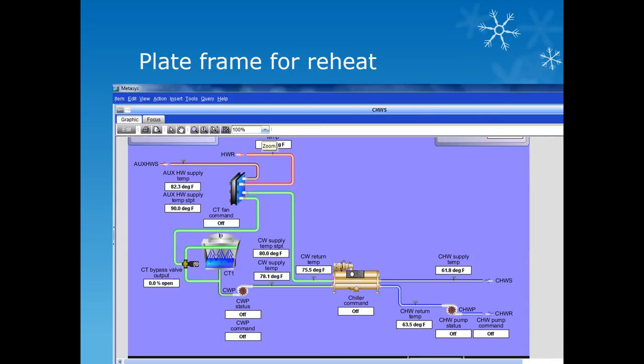In this graphic we see the typical layout of a plate frame system configured for reheat. Unlike the system configured for cooling, the plate frame system on this unit is used to heat the water for the hot water system. One of the drawbacks to this type of configuration is when the outside air temperatures are at a level where the chiller itself is not needed. When that occurs, you will need to provide some type of backup heating system, either a boiler or steam system.